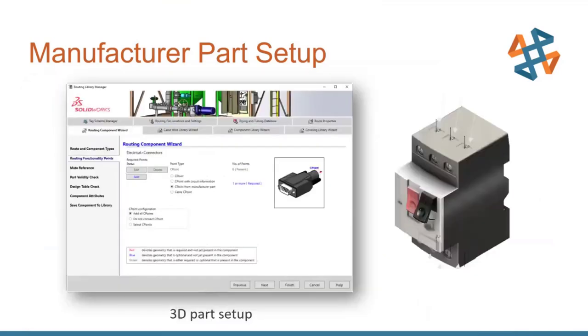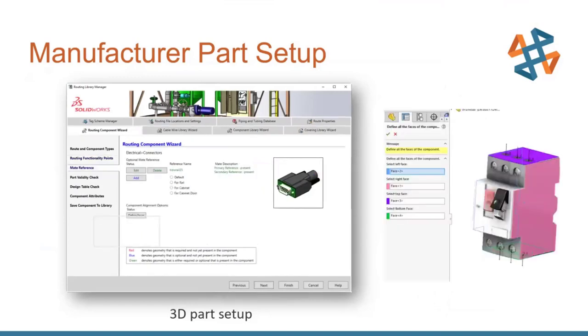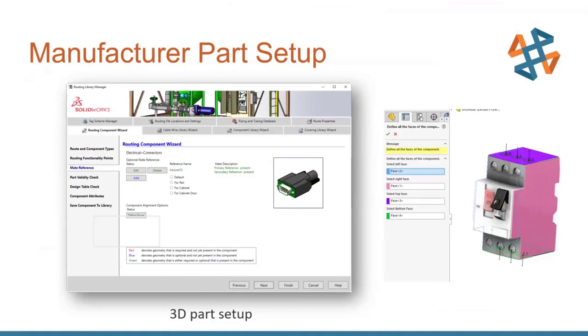If we have electrical 3D, we can set up our connection information from the manufacturer part. We grab our routing wizard, we open up that part, we hit add from manufacturer part, it's going to hand us all of the circuit information as it's defined in our database. That way when we connect something up in the schematic, we're able to route to it in 3D. From there, we can go a step further with our 3D parts. We can make them even more intelligent. Not only will they be able to route as they're defined in our schematic, but we can set them up so that we can insert automatically several parts and it will know how to space those accordingly. We can also create smart mates so that connectors, for example, will automatically snap into their mating connector. Or perhaps a component will snap onto a DIN rail for you.